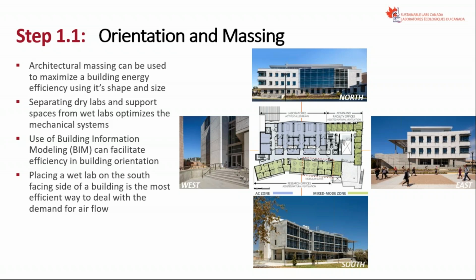Another programming lesson learned is that it's good practice to isolate HVAC systems for dry labs and support spaces from wet labs, separating the HVAC that serves dry and wet, to reduce the burden of the wet labs on the rest of the building.